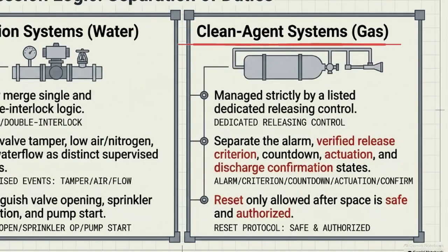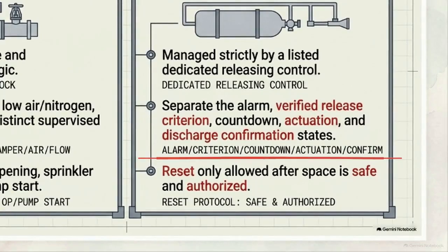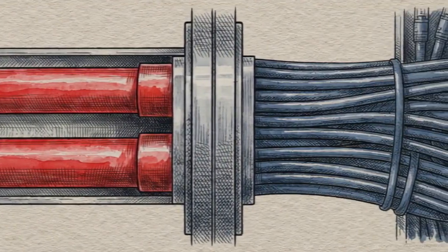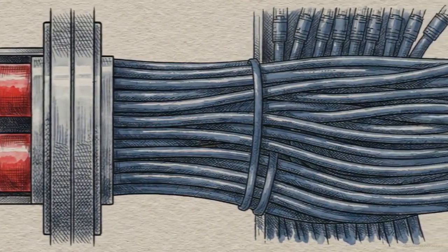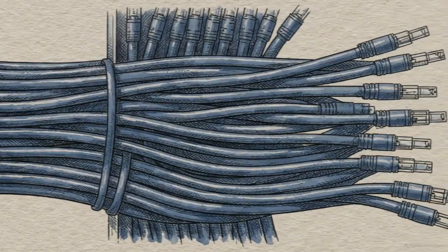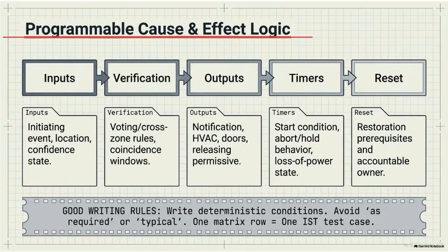We see this separation of duties applied to the most critical output, gas suppression release. Gas actuation must be managed strictly by a dedicated releasing control unit, ensuring the initial alarm is separated from verified countdown and discharge states. System resilience comes from isolating the authority of life safety components from the vulnerabilities of the broader IT network. We bind the hardware together using deterministic cause and effect logic, where every scenario is pre-calculated. Terms like "as required" are forbidden because every matrix row must represent a specific, testable outcome.